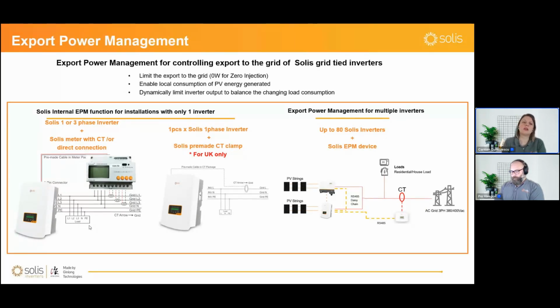So the only way to do that is to have a device connected at the grid connection point, after your loads, that can measure whether energy is going in or out from the grid. This information is sent to the inverter through RS485.